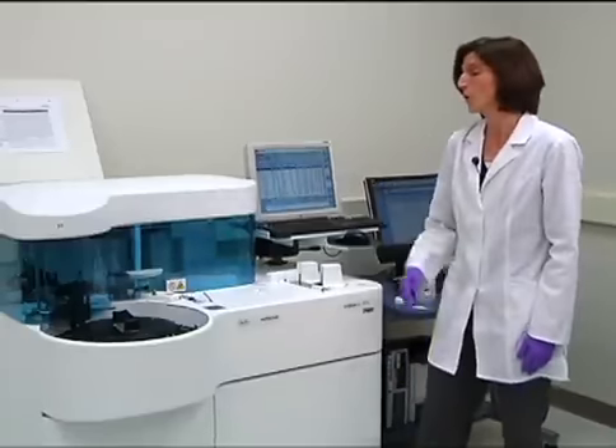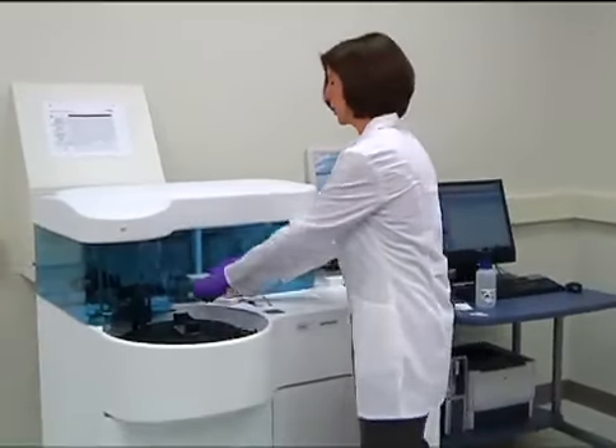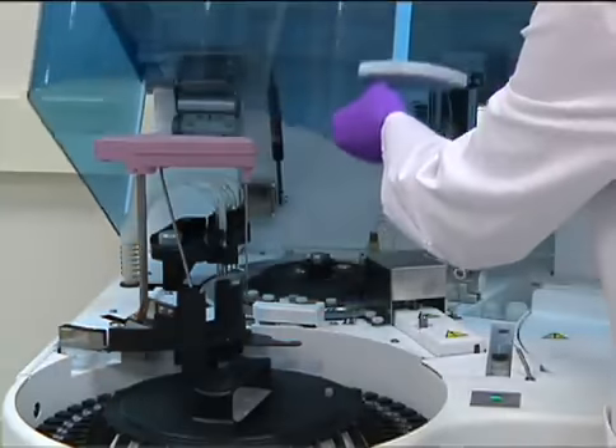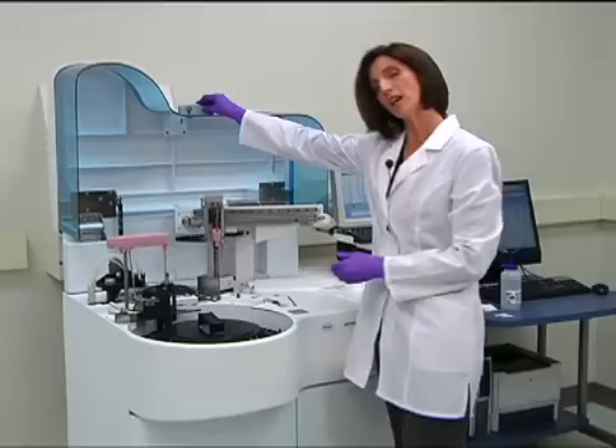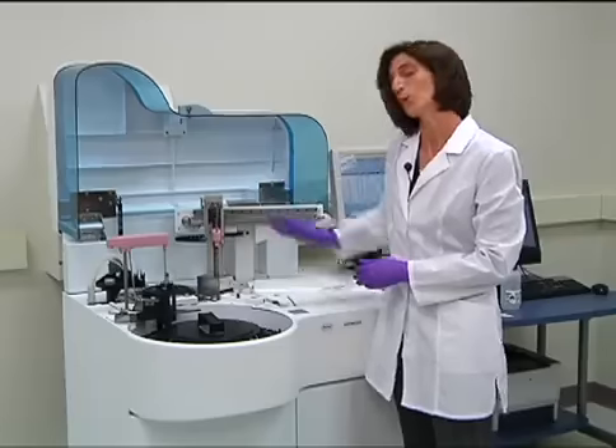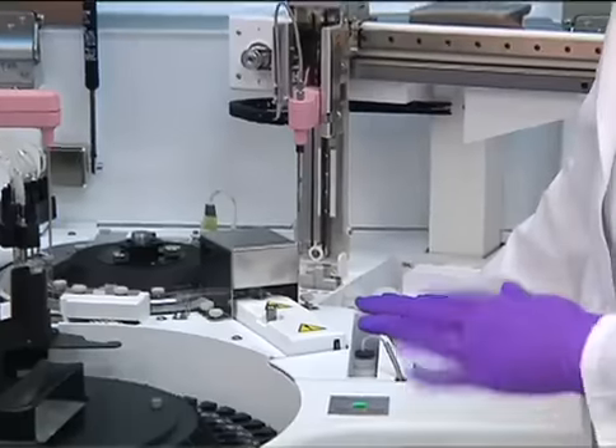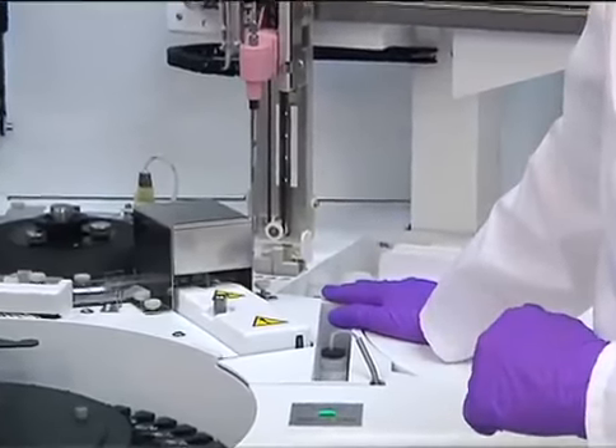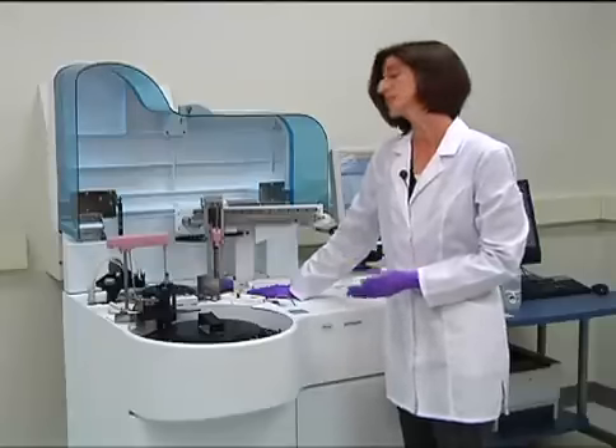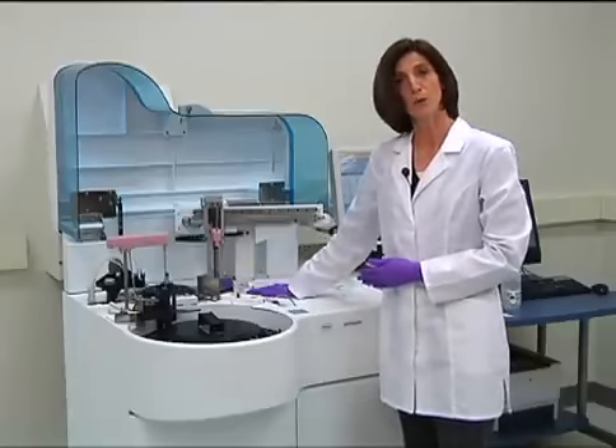Now we're ready to enable the maintenance mode, and this will allow us to perform our hands-on maintenance. Once the instrument's in maintenance mode, we will open the top cover. And before we actually perform the hands-on maintenance, we're going to check our ISE reagents and detergents that are on the analyzer. According to our load list, we would know what reagents need to be replaced.